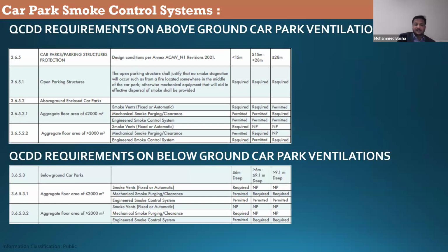You can have a smoke system also if the aggregate floor area is less than 2000. Suppliers, please excuse me, because this is what the code says. Normally, we used to provide smoke ventilation systems for all sizes of car parks, like 1000 square meter car parks. Also, we used to put jet fans and extract fans over there. But we do not need that if you have a smoke vent system and the car park is less than 6 meters deep. That's enough. I will explain how it is.